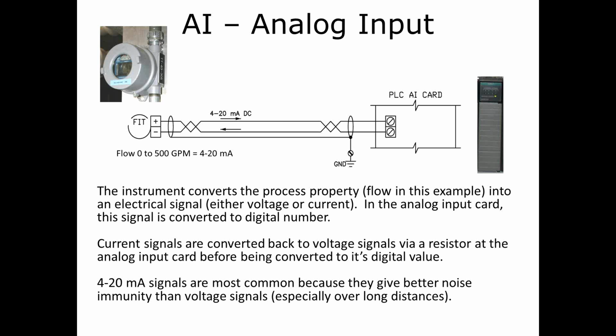And there are other signals that equipment can give out. Some instruments give a voltage out rather than a milliamp signal out. We try to use milliamp signals when they're available because they're the most common and they give better noise immunity than voltage signals, especially if you're going a long distance. On some instruments using voltages, if they're going a short distance, maybe a voltage signal is okay. But if you're trying to transmit over a long distance, you're going to want to use a milliamp signal.